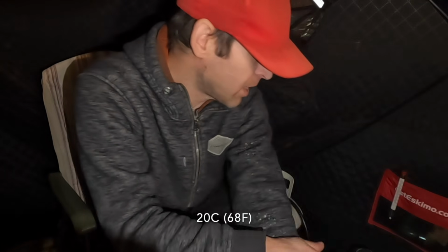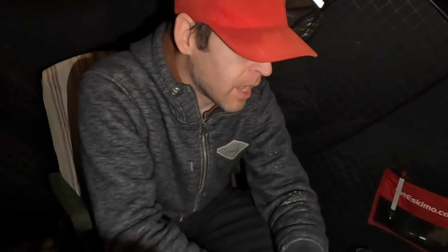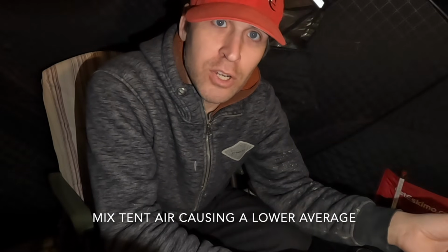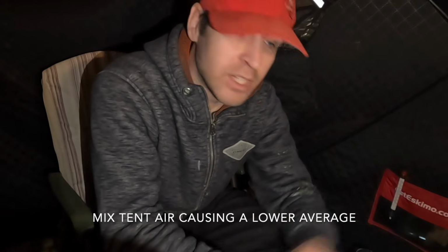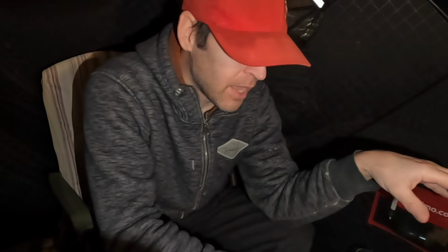So if we leave this run, which we are going to, it could possibly be 20-degree exhaust coming out of the heater, which would be, I don't know what in Fahrenheit, but yeah, it could possibly circulate ambient air enough that it pulls the temperature of the exhaust down to 20 degrees or something like that. So we're not breaking any laws of physics or anything like that, and what I said still stands true. The exhaust air can't be any cooler than the temperature of the air that is being blown over the exchanger.